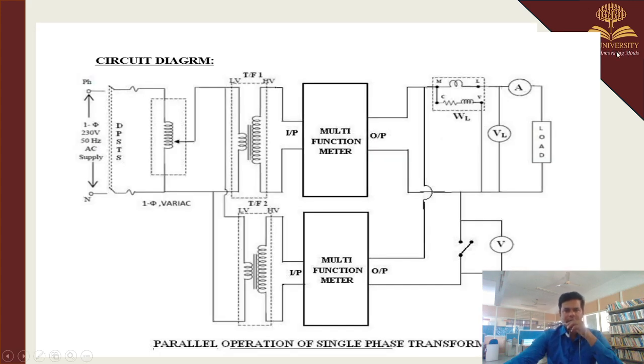So this is the actual circuit diagram. In the circuit diagram, we are using a single phase autotransformer, you can see this is a single phase variac. This is connected to our parallel operation of the two transformers. Here we can see this is one transformer TF1 and this is another transformer TF2. Here we have the LV winding and HV winding. This is P1 and this is P2, and P1 and P2 for the TF2 transformer respectively. The P1 of TF1 and the P1 of TF2 should be shorted and connected to the autotransformer. Next, the P2 and P2 are connected in parallel and connected to the single phase variac.